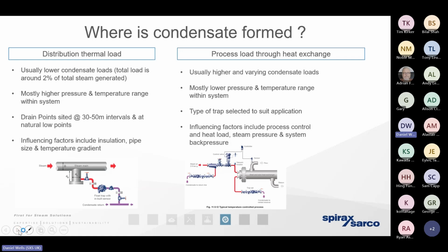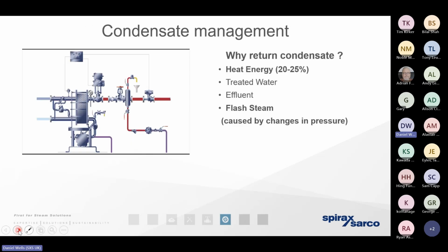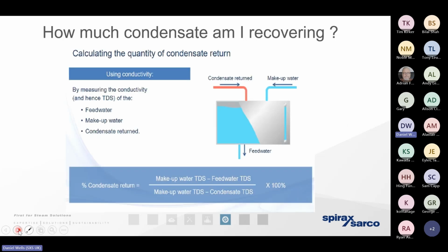So we've mentioned that condensate does have a value. That's why we need those steam traps. And the condensate is essentially going to exist wherever there is heat loss. So that can be in the pipework itself, or it can be at the processes. There is still a value. And we know that the steam tables tell us there's approximately 25% of the total heat energy of the steam retained within that liquid condensate. So if we've calculated our cost of steam correctly, we can understand the value of that condensate. If we've calculated steam at £60 per tonne, that condensate's got a value to us of approximately £15 per tonne. Of course, we want to return and recover as much of it as we possibly can.